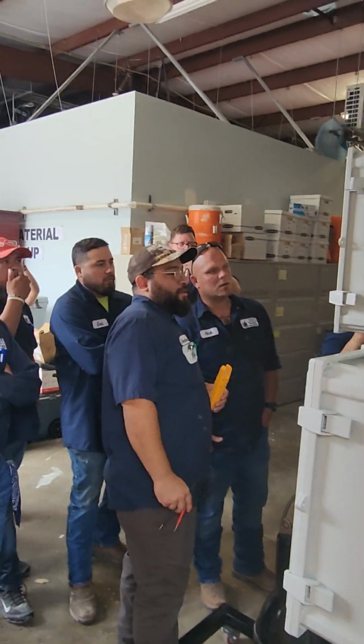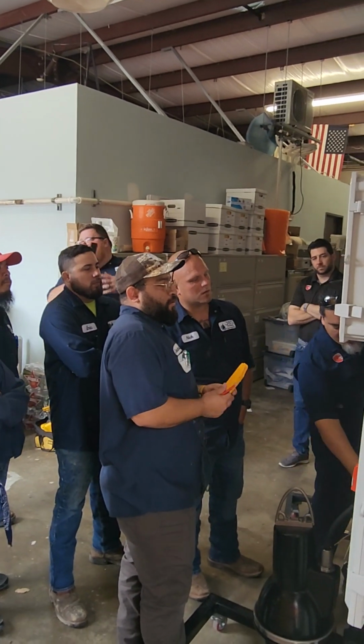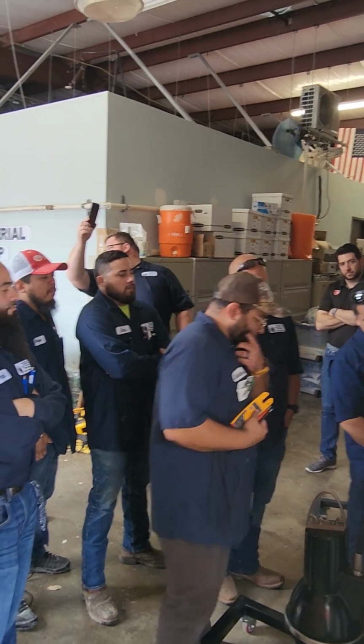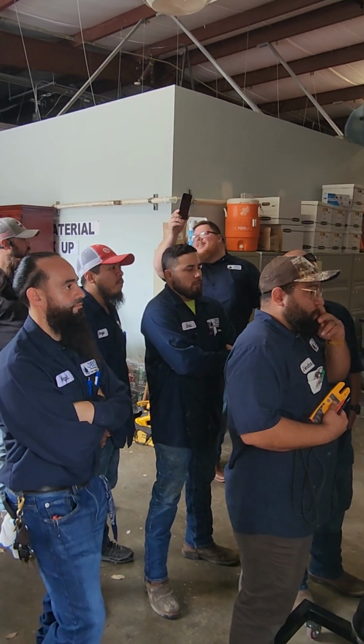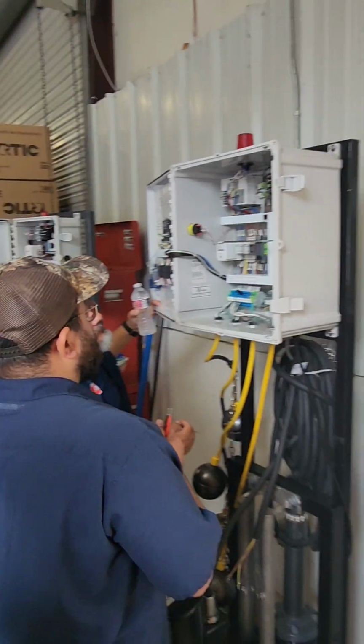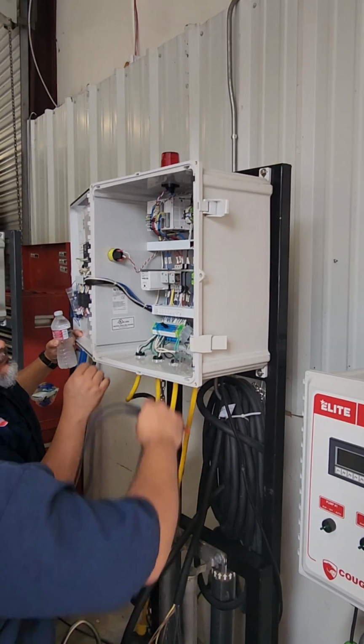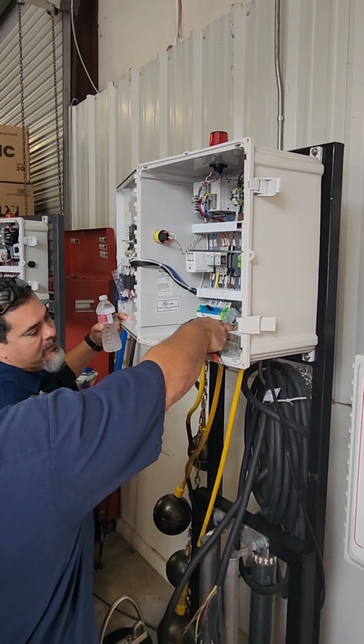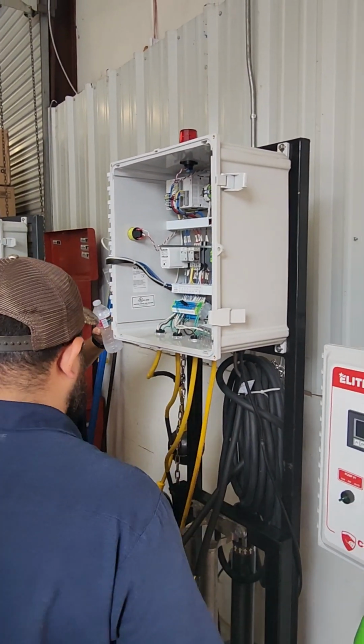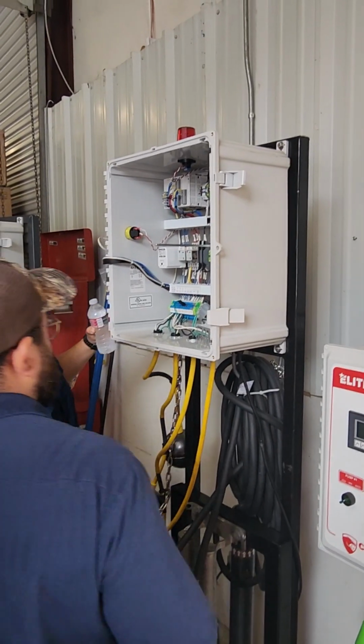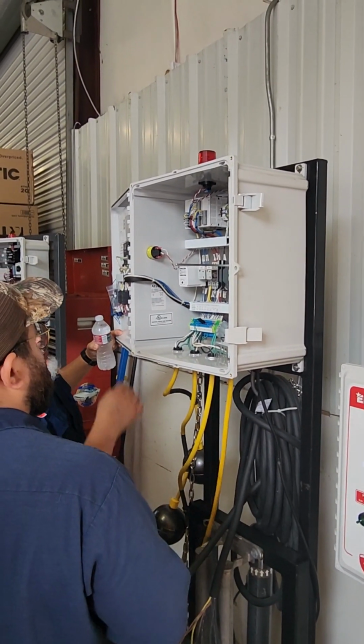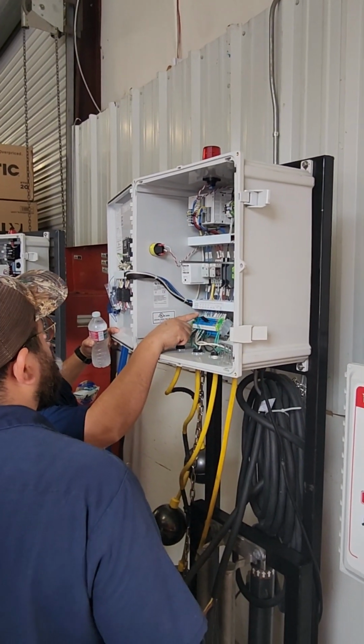So you have your, like I said, off float, on float, light float, alarm float. So you want to verify if your off float shuts off. Do these floats have a ground? Yes. Just do the big ones, yeah. Okay. So you would check continuity. Of course, you have to verify which is your off float and which is your on float.